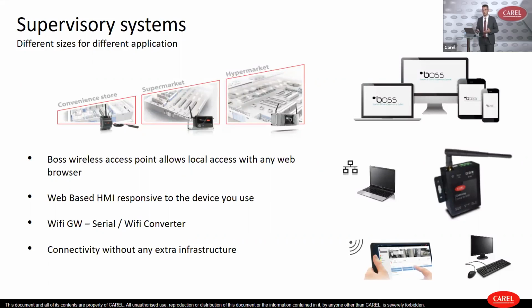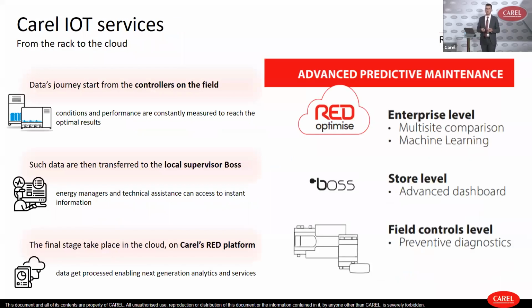on a local device like a laptop via Wi-Fi, or by remote if you have a remote connection. So you can log in and check how the system is working by looking at the different variables, by looking at the different conditions of the different devices connected. But this supervisory system, as you can see from these slides, is necessary to collect, of course, as I already said, all the variables from racks, cabinets, condensing units, and bring this information to our cloud platform that is called RED, our remote services platform.